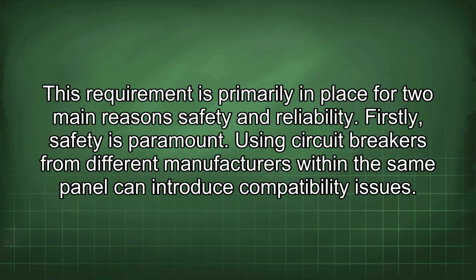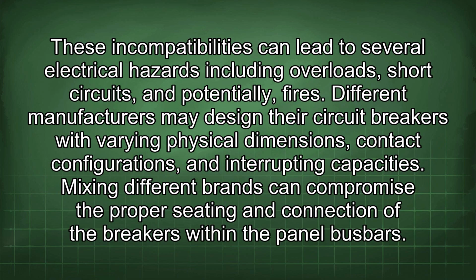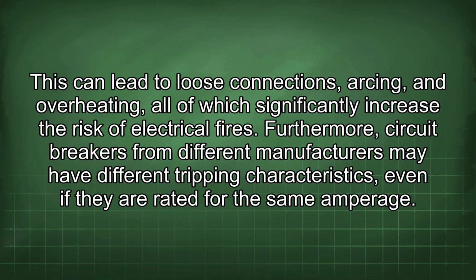Firstly, safety is paramount. Using circuit breakers from different manufacturers within the same panel can introduce compatibility issues. These incompatibilities can lead to several electrical hazards, including overloads, short circuits, and potentially fires. Different manufacturers may design their circuit breakers with varying physical dimensions, contact configurations, and interrupting capacities. Mixing different brands can compromise the proper seating and connection of the breakers within the panel busbars. This can lead to loose connections, arcing, and overheating, all of which significantly increase the risk of electrical fires.